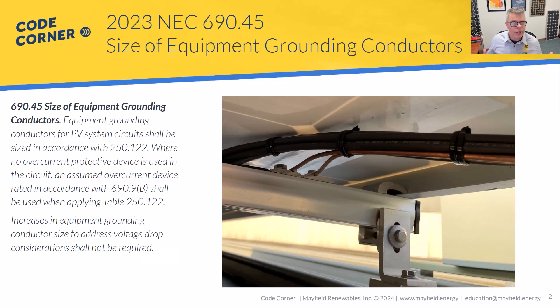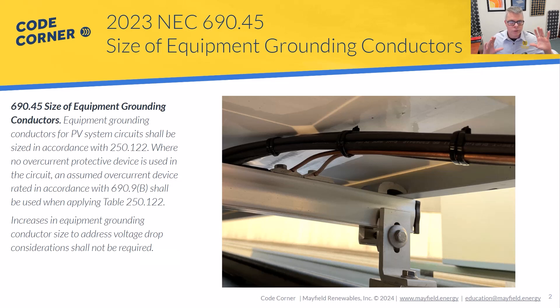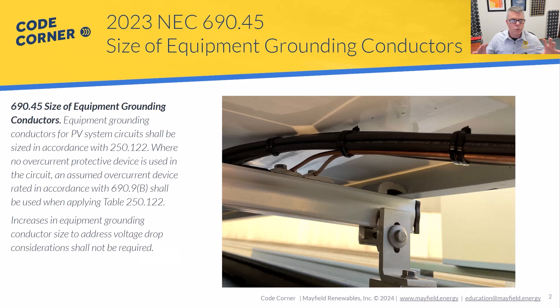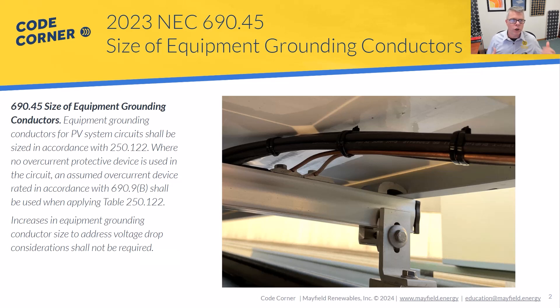The equipment grounding conductor section actually starts earlier in 690.42, so I recommend going and looking at that if you're not super familiar with it. I'd also recommend pausing and reading through the code language as I show it on the next few screens. So 250.122 as it relates to Article 690 — 690.45 says we're going to size our circuits based on that section.